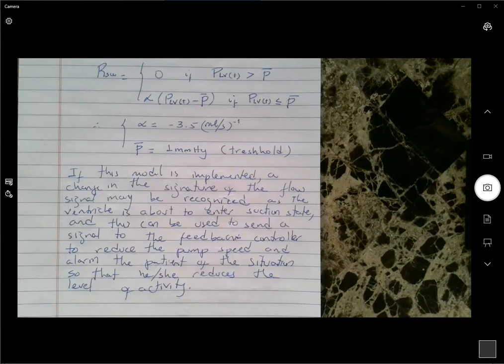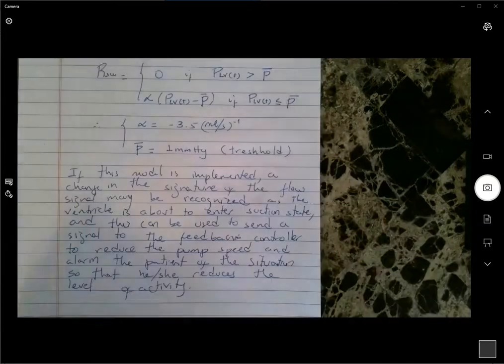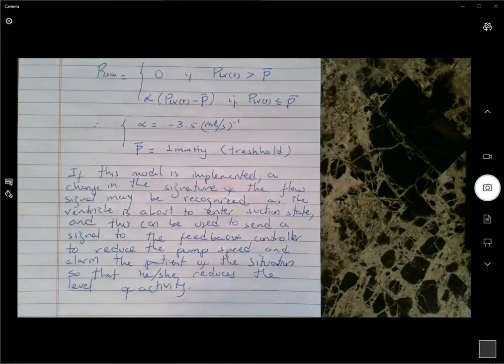But a very simple optical sensor can actually determine the pump speed, omega. So if you have the pump speed omega, you can calculate the pump head. With the pump head, you can calculate the pump flow. And if you plot the pump flow on the fly in situ, you can see if there are special patterns, if there are underlying harmonics in the signal, that can be a telltale sign that something bad is about to occur.